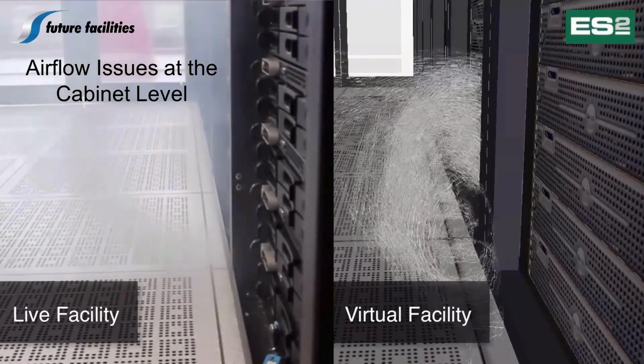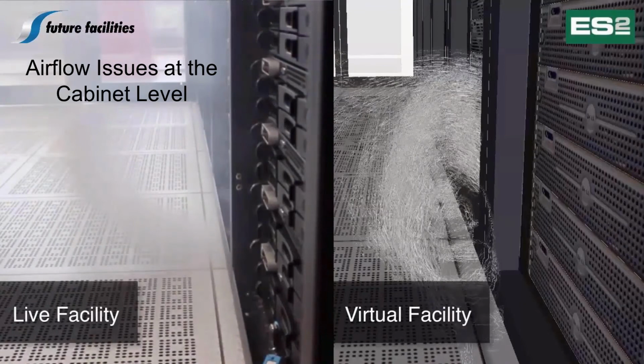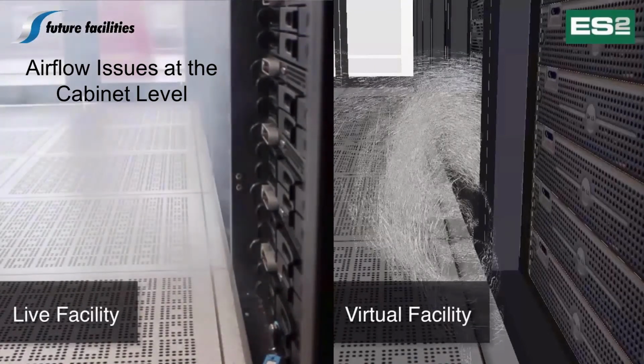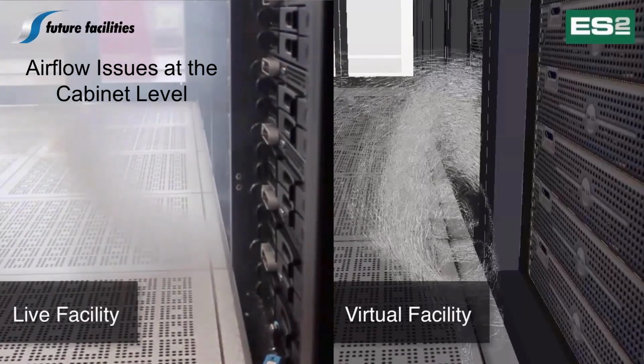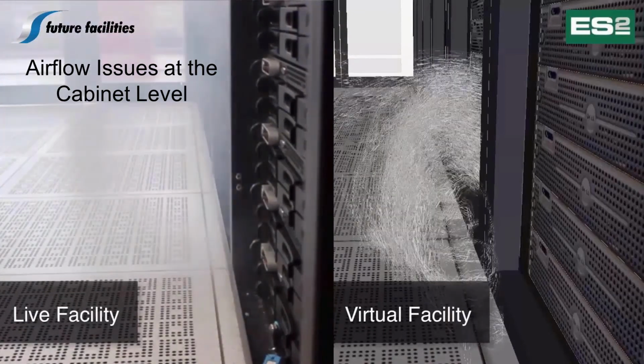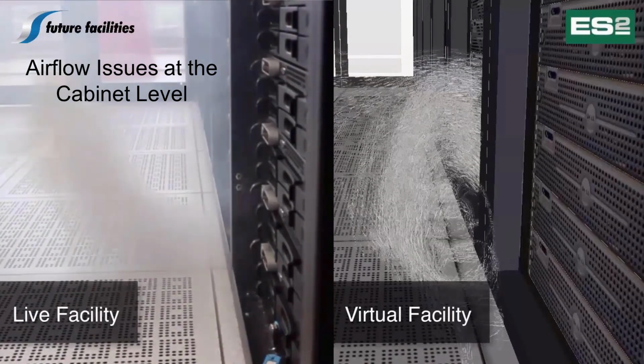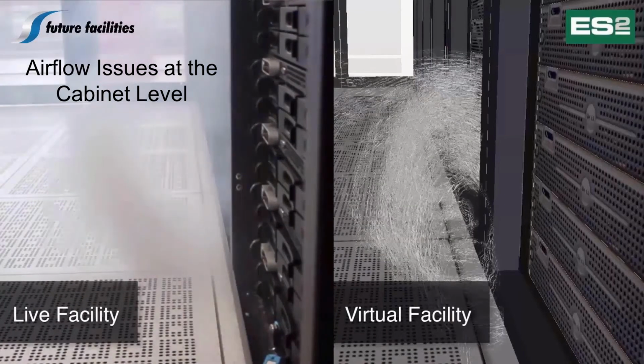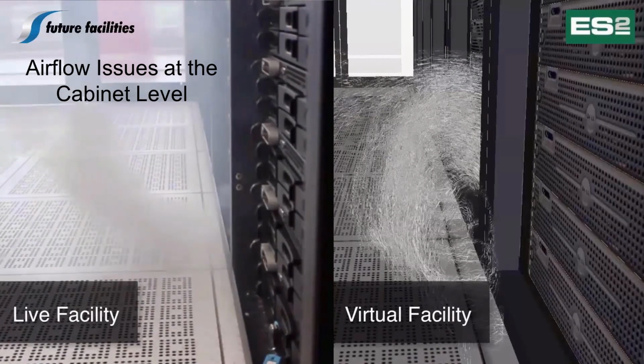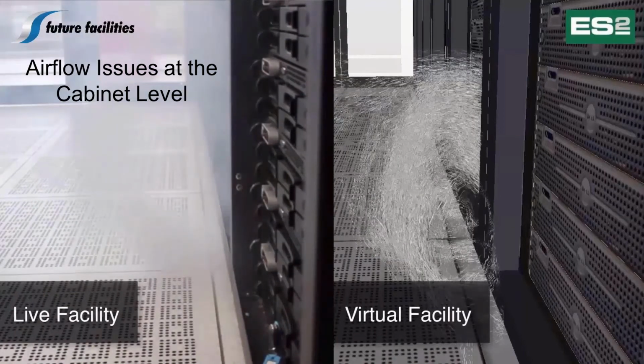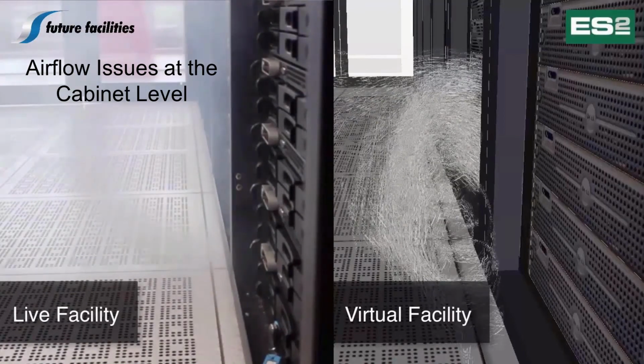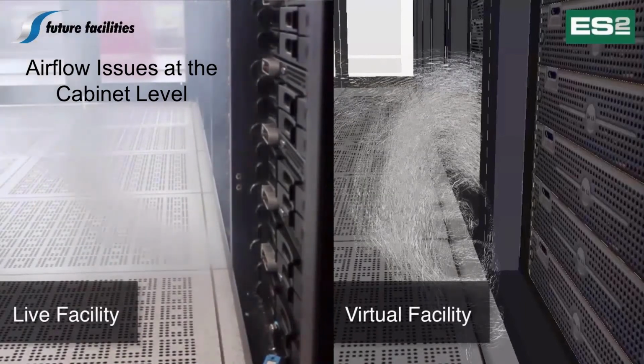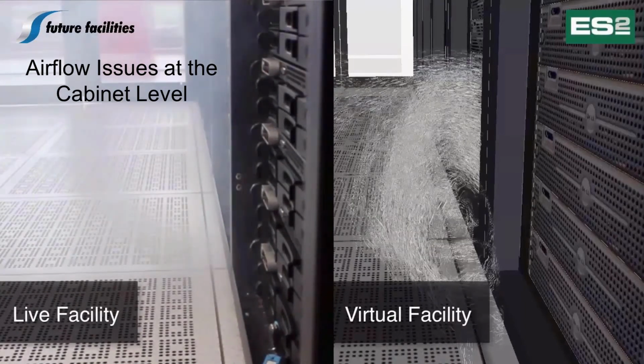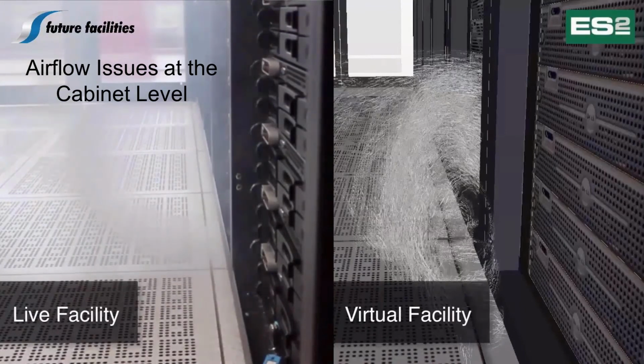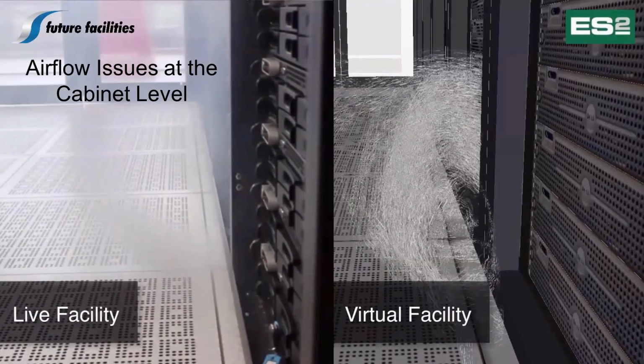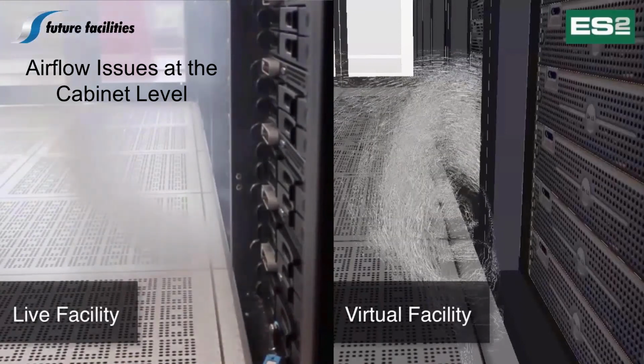Yeah, absolutely. One of the really important things to point out here is that this is a room where everything has been done very well. Best practices have been employed in all cases. We have blanking panels filling all open spaces. And if people will note, there's 2 full rows of supply tiles as well as doors on the end of the cold aisle. So this is a contained aisle, and yet it still suffers from this one last gap in that vertical plane at the intake of the servers.